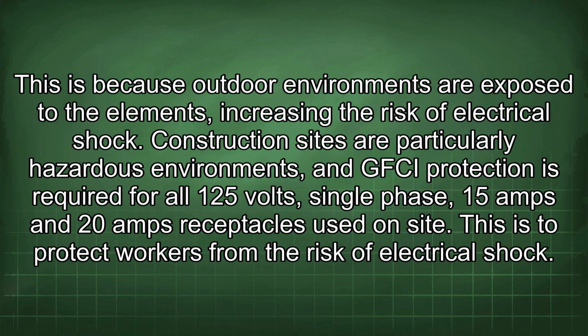Construction sites are particularly hazardous environments, and GFCI protection is required for all 125 volts, single-phase, 15 amps and 20 amps receptacles used on site. This is to protect workers from the risk of electrical shock.